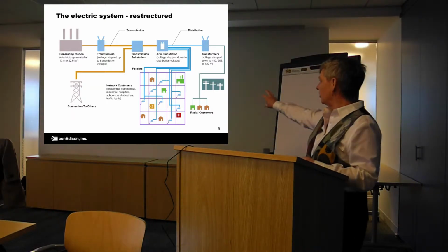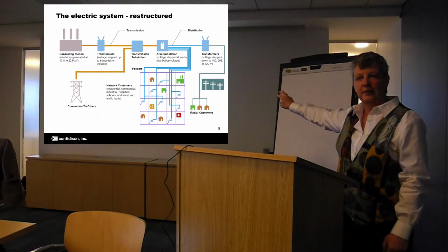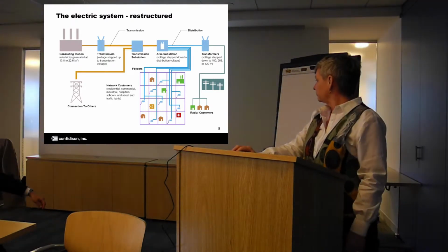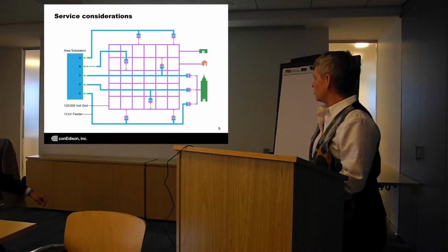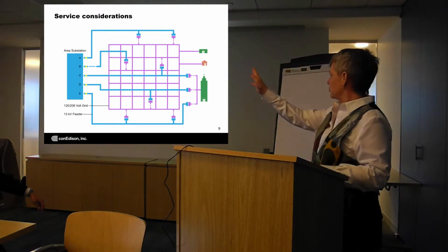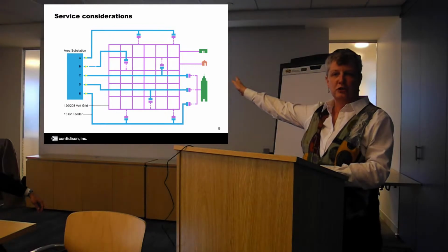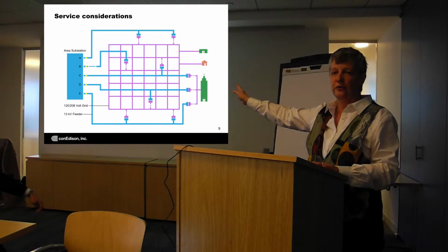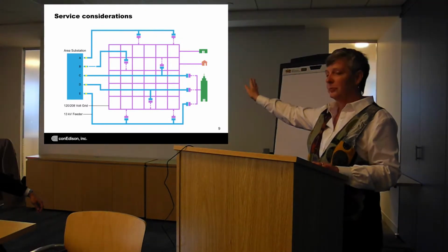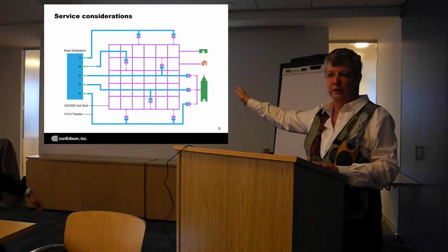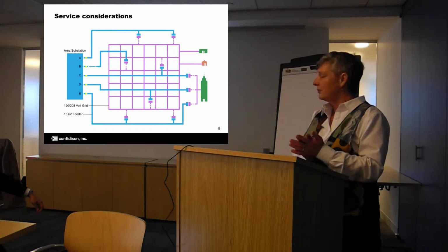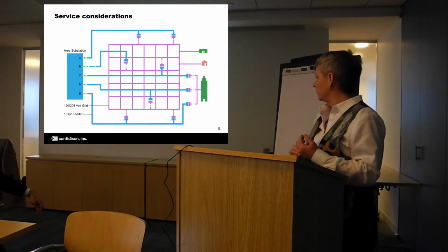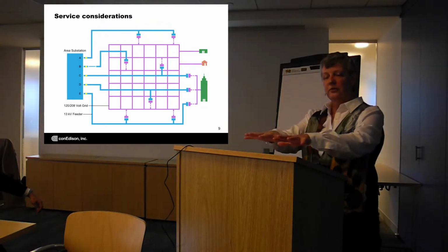And I'm going to focus on the electrical aspects of the grid and of the networked grid here. Just electrically, to think about it, you'll have transmission lines coming into the area station. I'm not showing them here, but imagine you have high voltage, 138 kilovolt or 345 kilovolt lines coming into the station. These would be underground if you're in the city. Coming out of that station, again underground, are 13 kilovolt feeders that go out into the street.